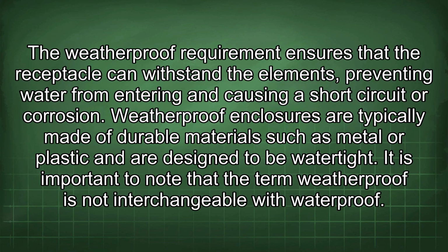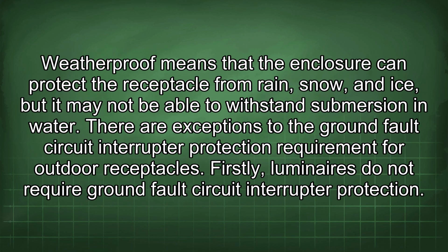The weatherproof requirement ensures that the receptacle can withstand the elements, preventing water from entering and causing a short circuit or corrosion. Weatherproof enclosures are typically made of durable materials such as metal or plastic and are designed to be watertight. It is important to note that the term weatherproof is not interchangeable with waterproof. Weatherproof means that the enclosure can protect the receptacle from rain, snow, and ice, but it may not be able to withstand submersion in water.